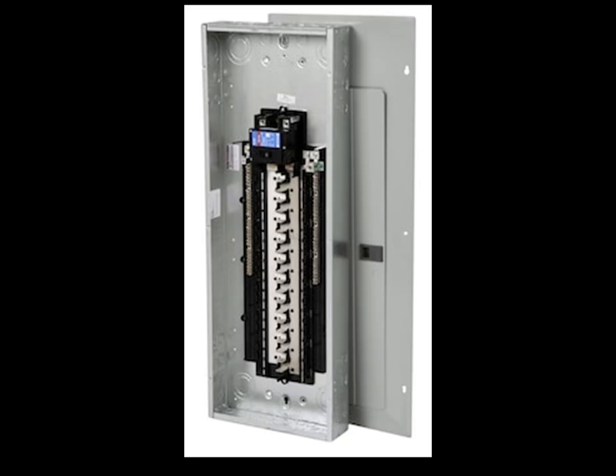My primary terminal box is a plug-on neutral PON load center. This is the type to have. Make sure you buy plug-on neutral breakers. As we discussed, plug-on neutral means that there's a neutral bar that each circuit breaker plugs into the full length of each side of the box. In non-plug-on neutral boxes, breakers only plugged into the hot line. Plug-on neutral breakers plug into both the hot line and the neutral.